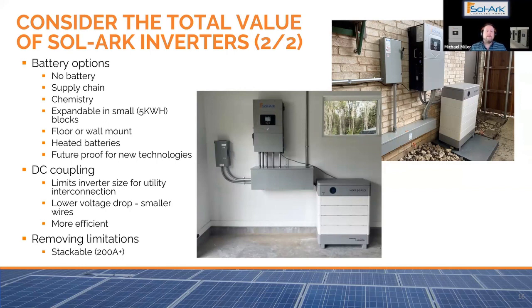With DC coupling, when I did an application for the utility in the past, I would have to tell them what my total inverter size was. And sometimes there are limitations for interconnection. Those need to be accounted for, and you may place yourself out of a certain category if you do an AC coupled system, if they're looking at the total inverter size.